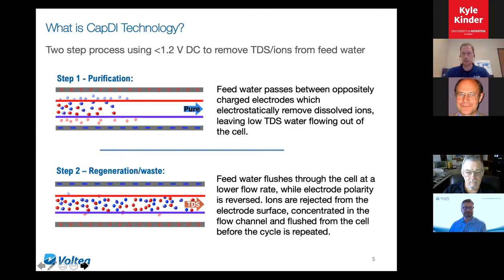We run as a batch process, so we run in two phases. The first phase is purification, where we're pulling those ions out of the system. Then we need to regenerate. How do we do that? We flip the applied potential, so the positively charged electrode we flip to negative, and the negatively charged electrode we flip to positive. The result is that anything held against those electrodes gets repelled away from them. It will be concentrated in the flow channel, and then we use a small amount of water to flush that flow channel out and flush that concentrate down to drain.